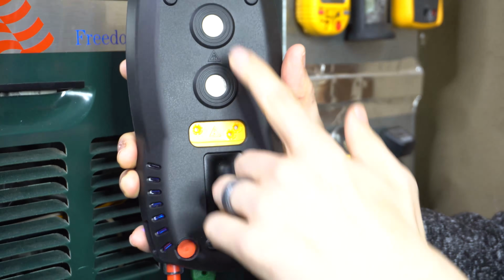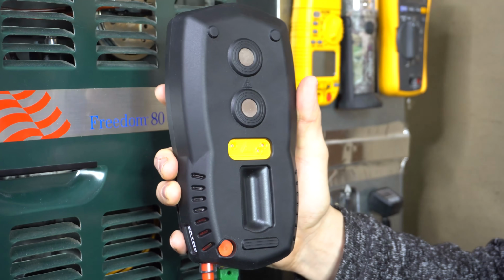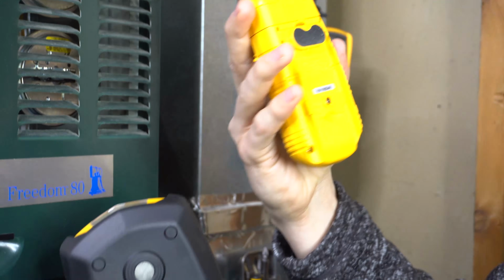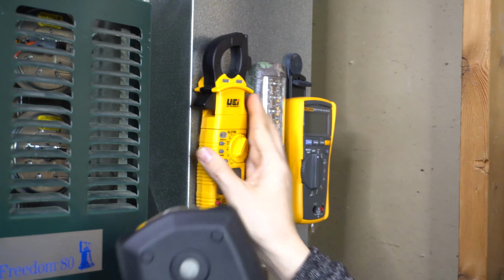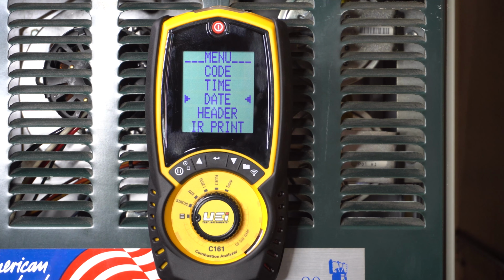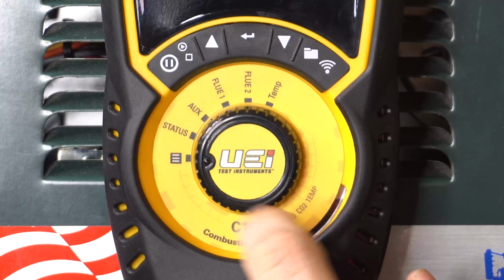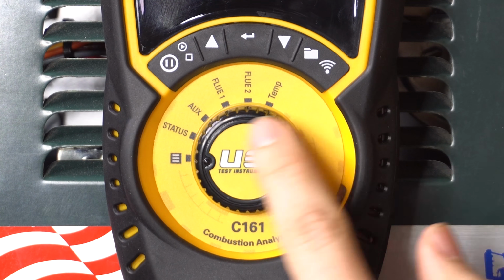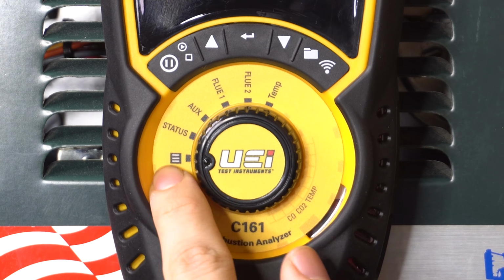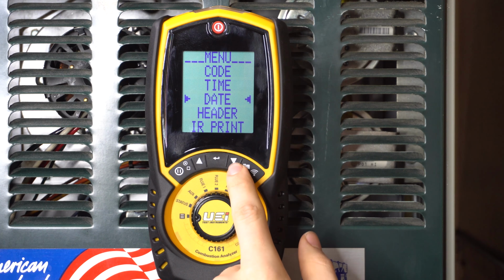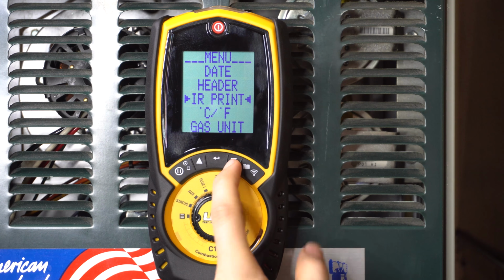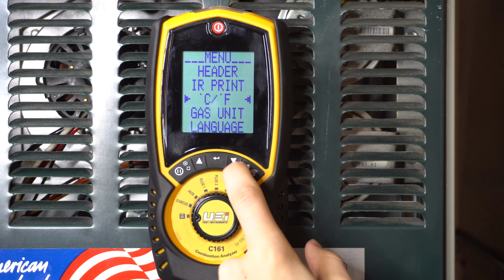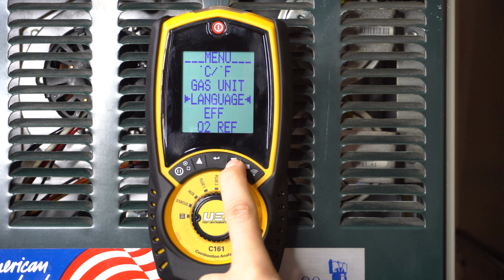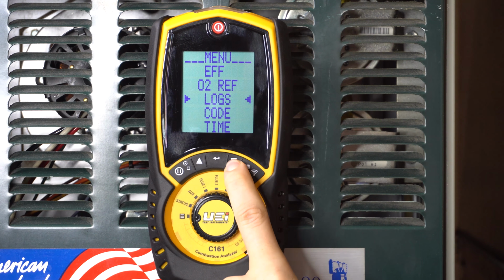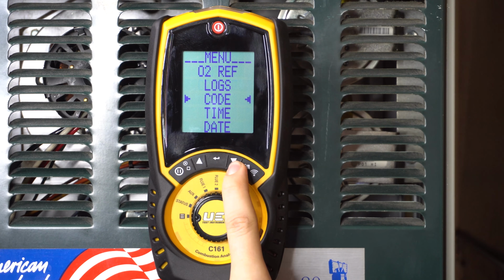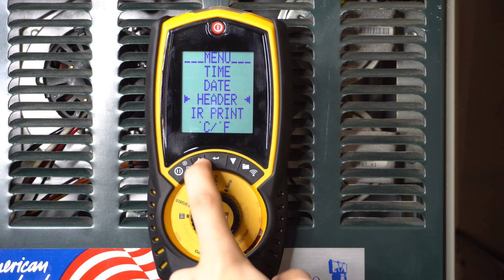And my favorite part, of course, is the magnets in the back. Any meters or analyzers that have magnets in the back, just like the UEi meter I have here, I'm definitely friends with them. Okay, so it's done purging, and just so you have a rough idea of what calculations and readings this analyzer can make, I'm just going to quickly go over all the menus over here on the dial setting. So right now it's set to general settings, and that's nothing too interesting. You can just change the date, the header, infrared printer, you can change between Celsius and Fahrenheit, gas units, what language you want to use, efficiency, what O2 reference you want to use, logs, it can store up to 30 logs, you can put a password on it, and general settings like that.